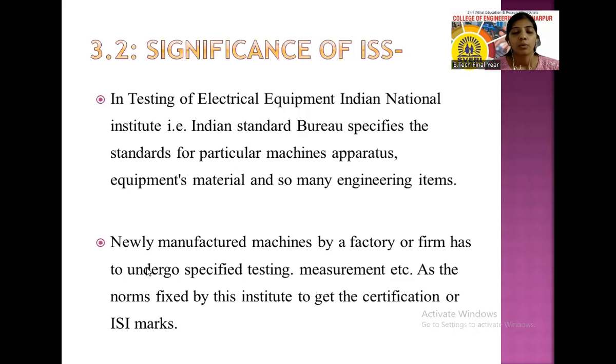So newly manufactured machines by a factory or firm have to undergo specified testing. Whenever the machine is manufactured in an industry or factory, it should be tested before selling. This includes measurement of insulation, measurement of resistance of the winding, high voltage test, reduced voltage test, no load test, momentary overload test. All these tests should be done before selling the equipment.